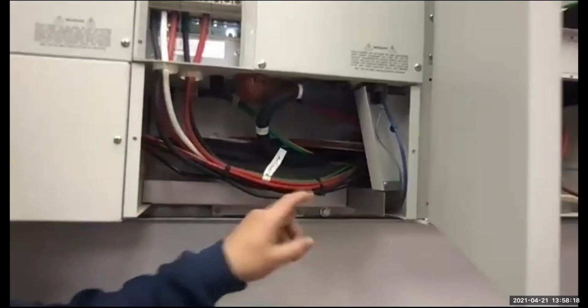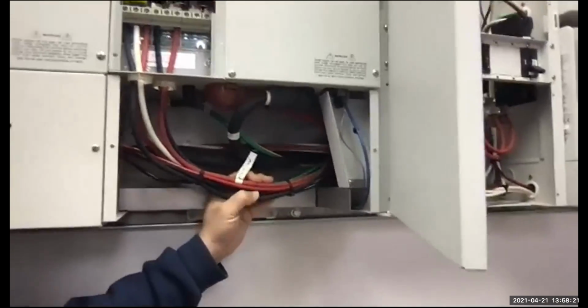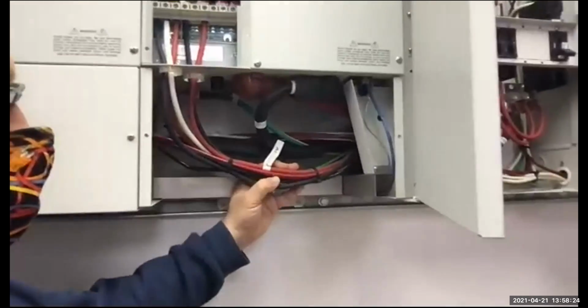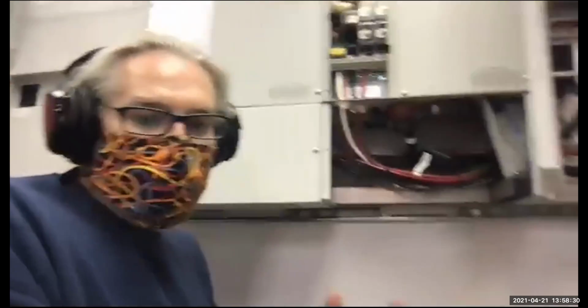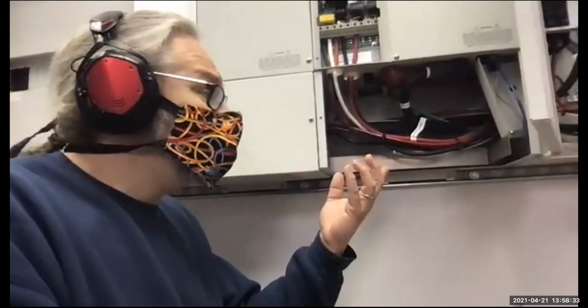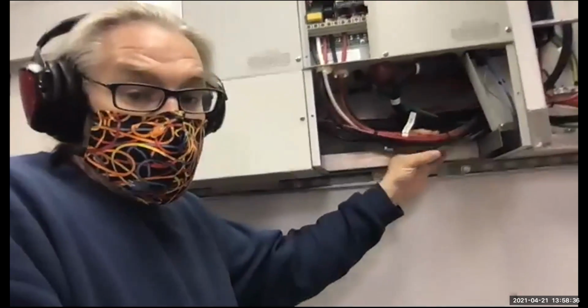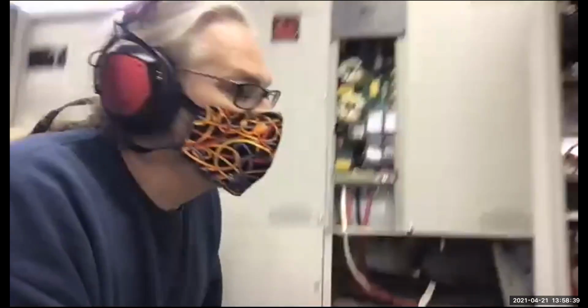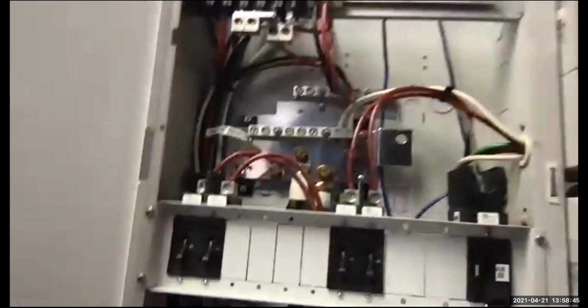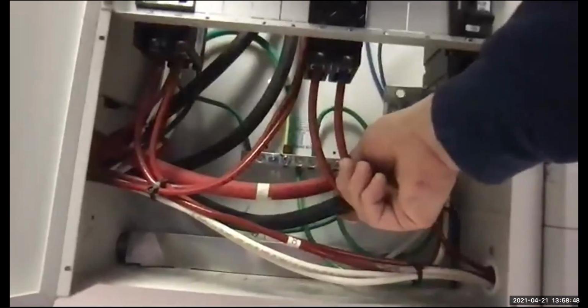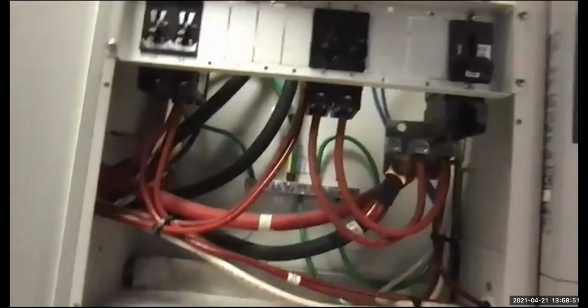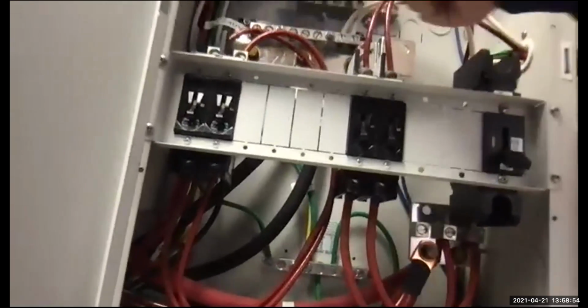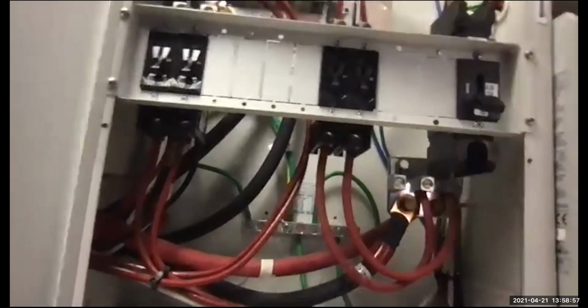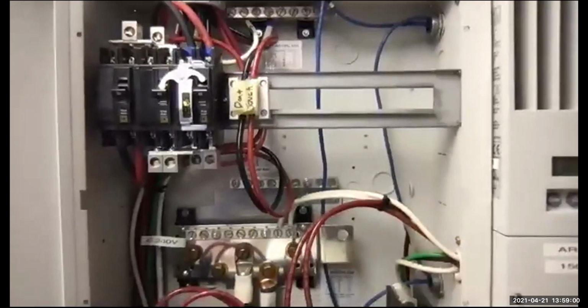Now we know that we want number 6 because our conductors are number 6. So if we're running number 6 wire, we did all our wire calculations like we're supposed to, right? Now that we have number 6 for our power conductors, all these wires here, every single one except these big fat ones. These big fat ones are 4-aught, for our batteries. As we've learned, we want to run with 4-aught. These right here are all number 6. Number 6 can handle a certain ampacity.